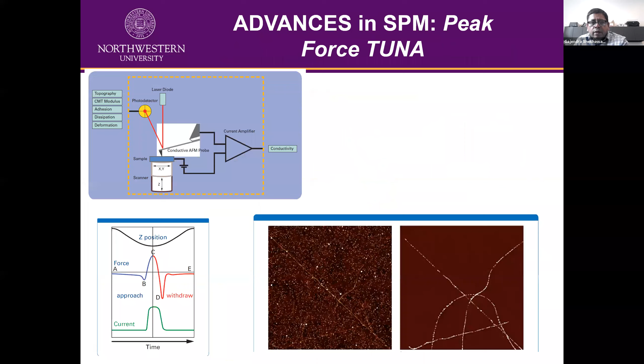So having said that, we then have PeakForce TUNA, which is tunneling AFM, or tunneling current measurements. You can see here on the bottom left in the figure, usually we use a typical conducting AFM probe. In traditional conducting AFM imaging, the tip was putting a lot of force on the sample surface. These cantilevers are coated with a pretty thin metallic layer. When the cantilever interacts with the sample surface and applies a large force in contact mode, the coating rips off. It's pretty troublesome: in the middle of your experiments, your coating is not there and you're not getting your image. So that was a problem.